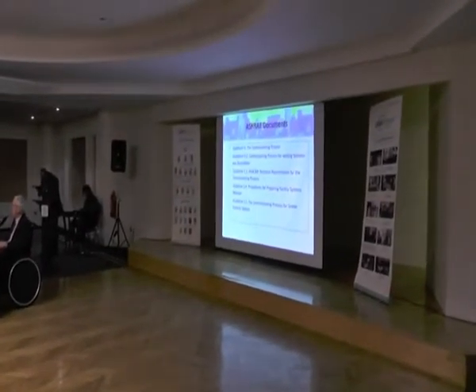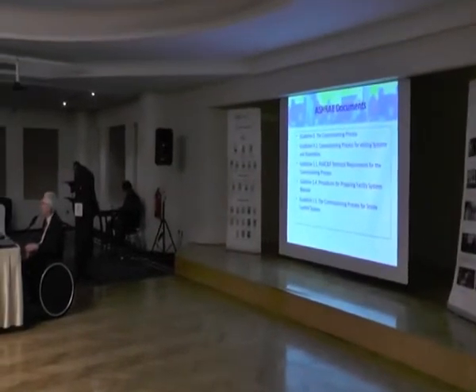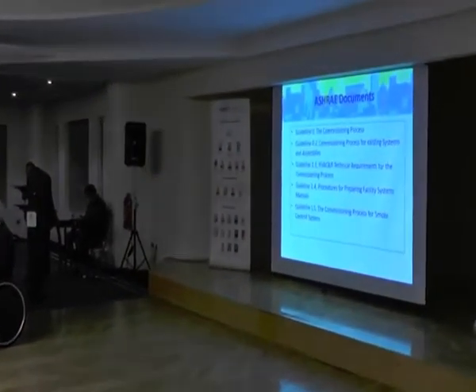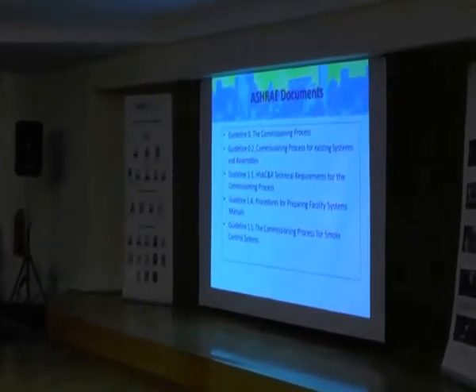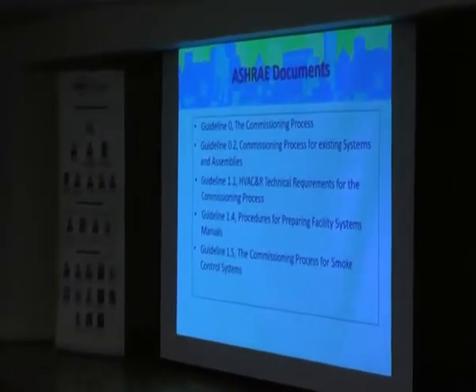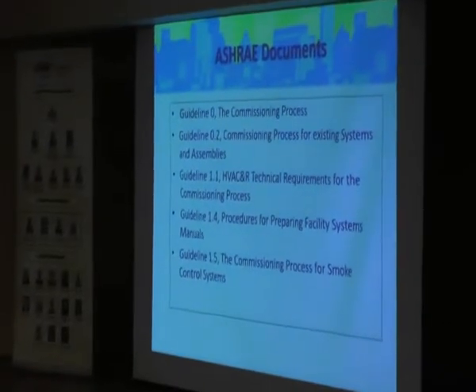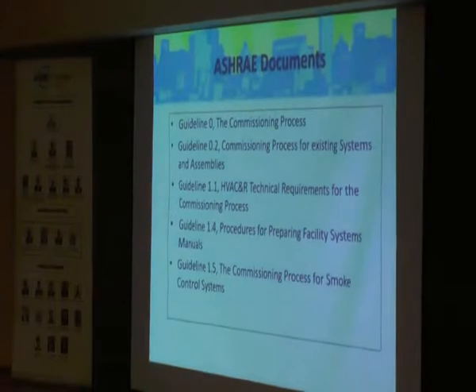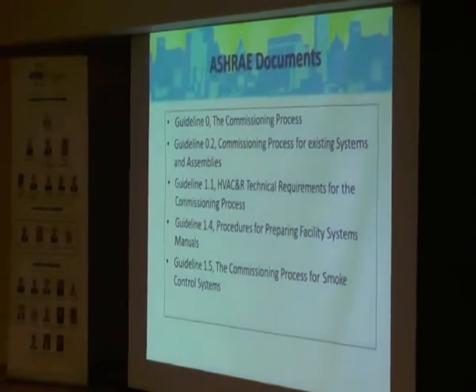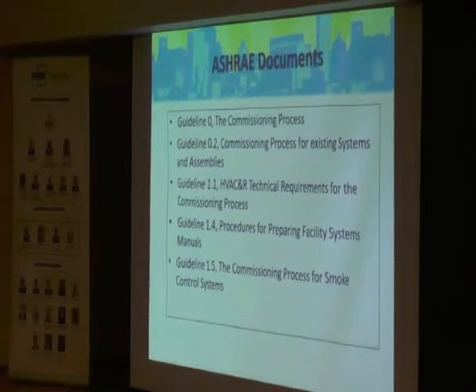ASHRAE has developed a series of excellent documents for guidance in the techniques of the commissioning process, actively pursuing various activities in commissioning. Guidelines 0 and 0.2 offer approaches to complete commissioning for new and existing facilities. Guideline 1.1 sets up the technical requirements for HVAC and R systems, particularly useful for those of us in this room. Guideline 1.4 addresses the essentials for a systems manual, and Guideline 1.5 is specific to smoke control systems. Commissioning procedures may be applied to any building system, including envelopes, emergency management systems, etc. If many different systems are commissioned, a commissioning management professional is needed for coordination of the project.